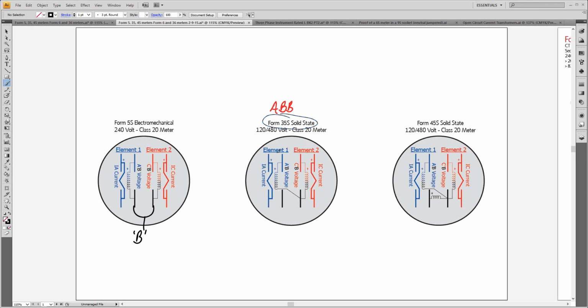We install the 35S into the same socket. When we do that, this jumper is okay to leave in place, because if I leave it in place and make the connection here between the two and still have B phase here, nothing inside the meter is connected to this terminal, so leaving this jumper in place will not hurt anything. But if you were installing a new one, you'd really only have to put B phase to the right center bottom terminal, because the potential coils in the 35S are tied to that point. So you wouldn't have to have the jumper, but if you have a jumper and replace the 5S with the 35S, there's no problem just leaving it wired exactly like it was.